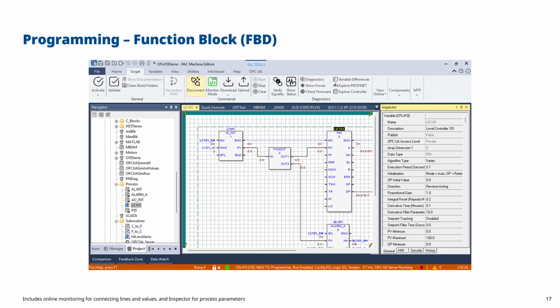So I've got a PID routine here with alarms. I've currently selected the LIC101 block, which is a process-oriented block. As well as all the parameters, by opening up the inspector we can see more detailed parameters for the PID function, such as its description, level controller 101, how it's operating, how it's initialized, and about two-thirds down you can see the actual PID values: a proportional gain of 1, an integral of 0.2, and a derivative of 0.1.